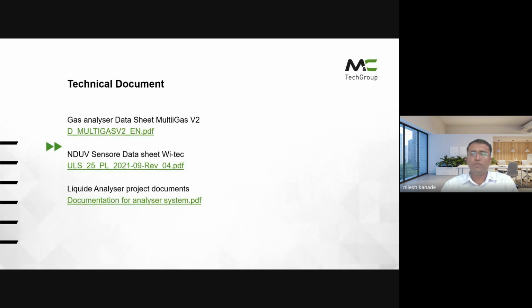This is the physical equipment, which has a display. On that display, it shows the measurement component readings, the name of the components like carbon dioxide, and the measurement values in percentage or ppm. Along with that, the equipment also gives output in the form of digital output, like 0 to 1 volt for the range, and 4 to 20 milliamps.